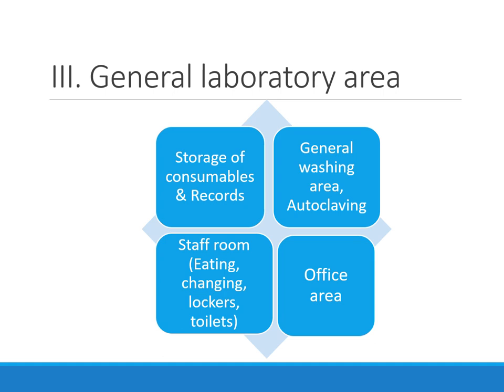The general laboratory area has no active processing and testing of specimens, but is necessary for the proper functioning of a complete laboratory. Clean, dry, and safe areas must be provided for storage of consumables, reagents, and testing records. There must be a general washing and cleaning area for reusable items, and an area for autoclave, hot air oven, and other sterilizing equipment that generate a lot of heat. The laboratory must have a staff room with lockers and toilets where staff may eat or change clothes, and an office area to maintain staff records, purchase records, and communications.